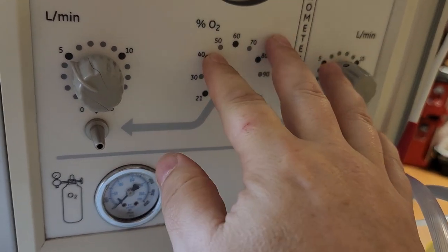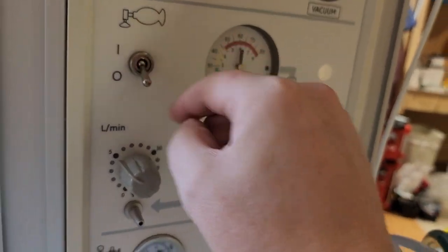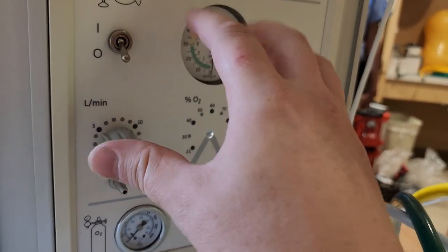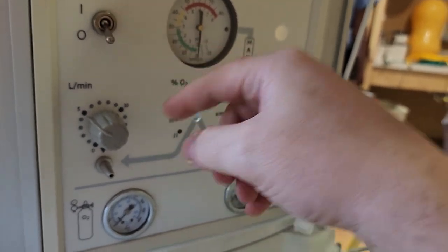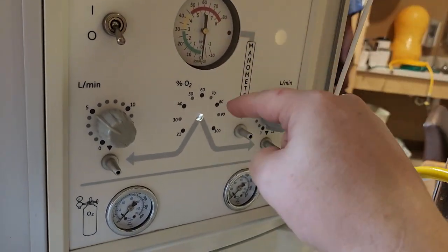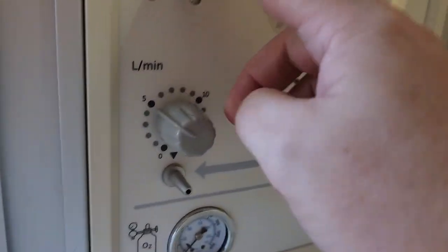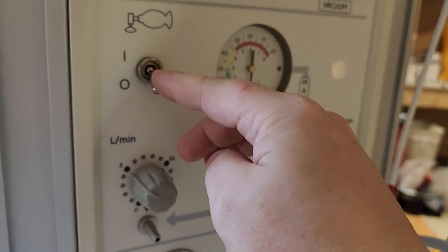So you can find this during a PM, but here's the thing: you have a switch right here that flicks on and off the blender. If this is in off position and your blender has air coming out, then you know something's wrong. It's actually the switch right here. The switch right here is the problem.